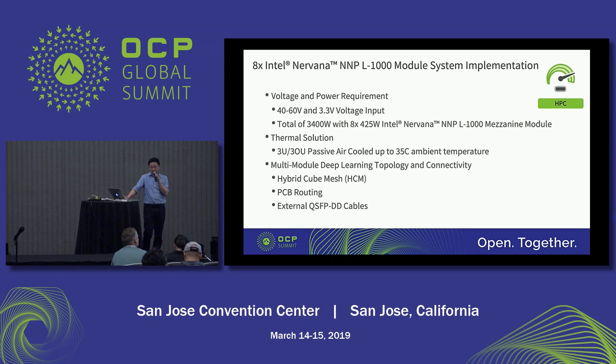I would like to talk about the requirements on the system implementation. The NNP module only supports 40 to 60 volts and 3.3 volts. The 40 to 60 volts is used to power up the NNP module, and the 3.3 volts is just for low power module management. The thermal solution supports 3U passive air cooling up to 35 degrees ambient temperature. Based on the OAM spec analysis, with a 3U air cool heat sink it can support up to 450 watts.